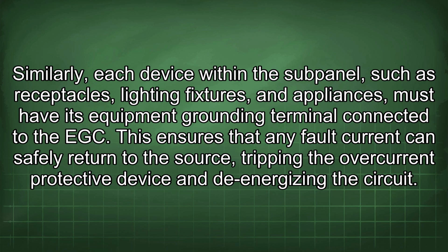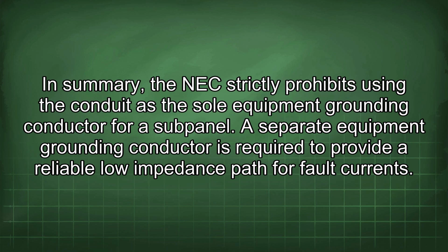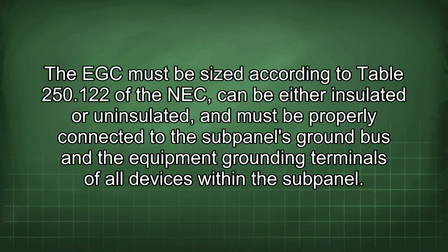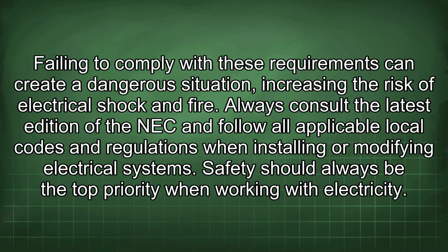This ensures that any fault current can safely return to the source, tripping the overcurrent protective device and de-energizing the circuit. In summary, the NEC strictly prohibits using the conduit as the sole equipment grounding conductor for a subpanel. A separate equipment grounding conductor is required to provide a reliable low impedance path for fault currents. The EGC must be sized according to Table 250.122 of the NEC, can be either insulated or uninsulated, and must be properly connected to the subpanel's ground bus and the equipment grounding terminals of all devices within the subpanel. Failing to comply with these requirements can create a dangerous situation, increasing the risk of electrical shock and fire. Always consult the latest edition of the NEC and follow all applicable local codes and regulations when installing or modifying electrical systems. Safety should always be the top priority when working with electricity.